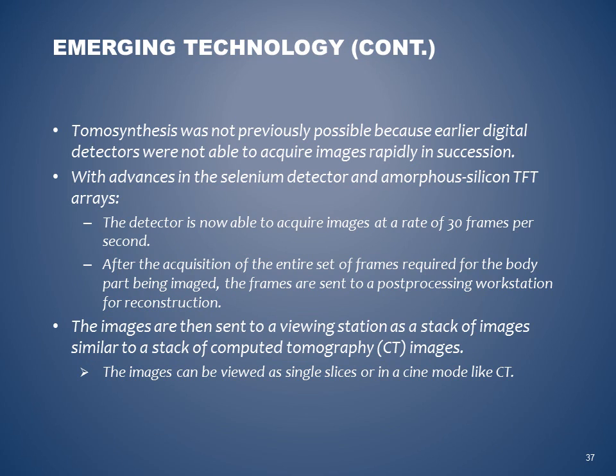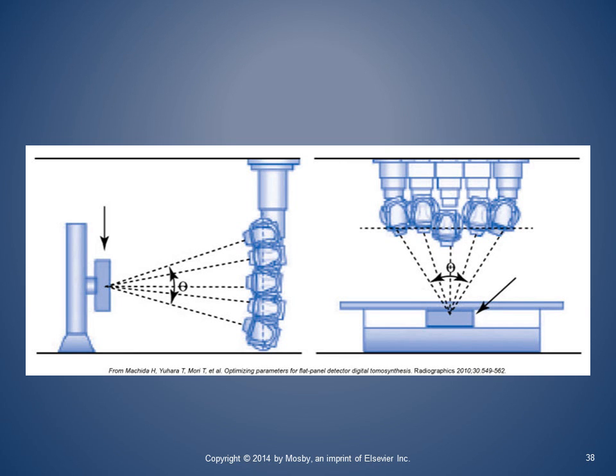Tomosynthesis was not previously possible because earlier digital detectors were not able to acquire images rapidly in succession. With advances in selenium detectors and amorphous silicon TFT arrays, the detector is now able to acquire images at the rate of 30 frames per second. After the acquisition of the entire set of frames required for the body part being imaged, the frames are sent to a post-processing workstation for reconstruction. The images are then sent to a viewing station as a stack of images, similar to a stack of computed tomography images. The image can be viewed as single slices or in a cine mode like CT. This is just showing you an example.